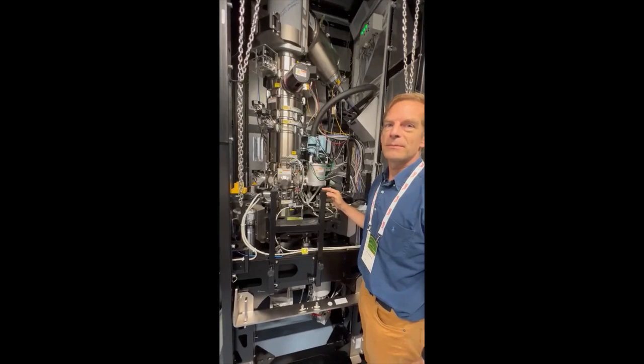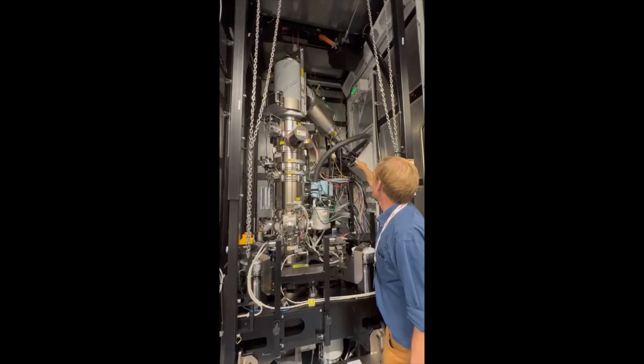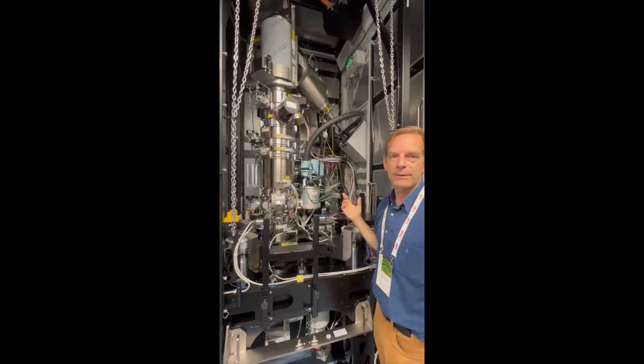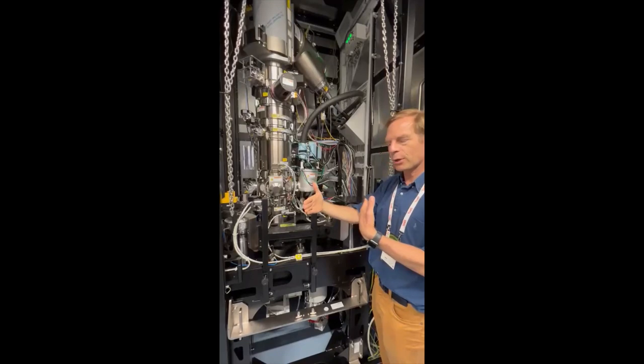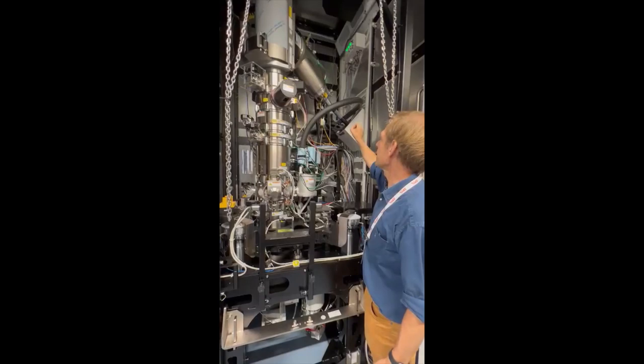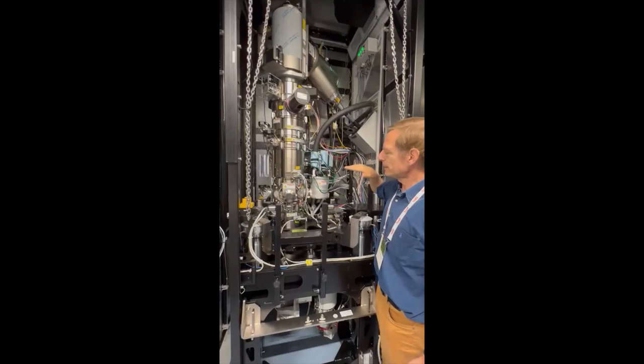The 300,000 volts acceleration comes through that black cable that goes out. In the back is a tank that makes 300,000 volts. 300,000 volts is a lot, so you need a good cable. I think you have 10,000 volts per centimeter, so 300,000 volts could jump over 30 centimeters if it goes through air. In the cable it's better insulating than air, of course.